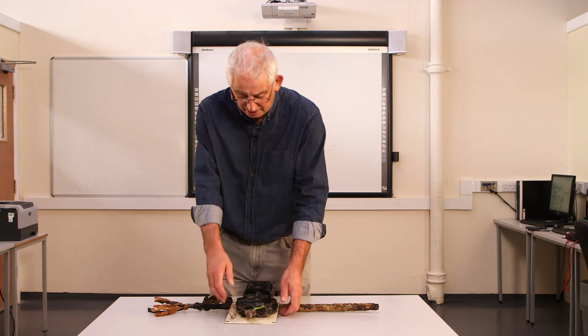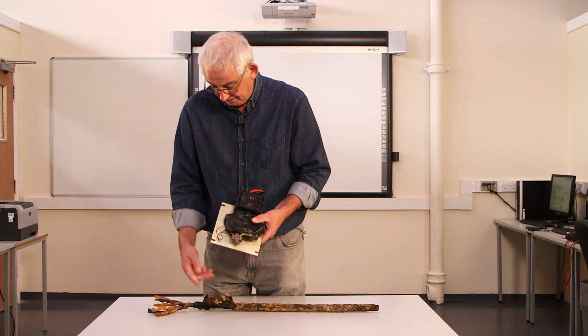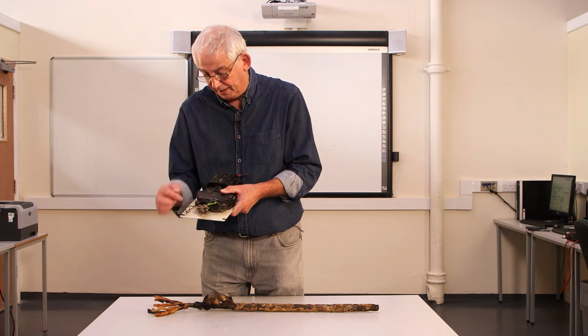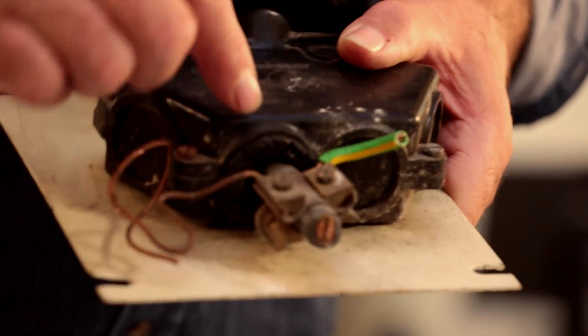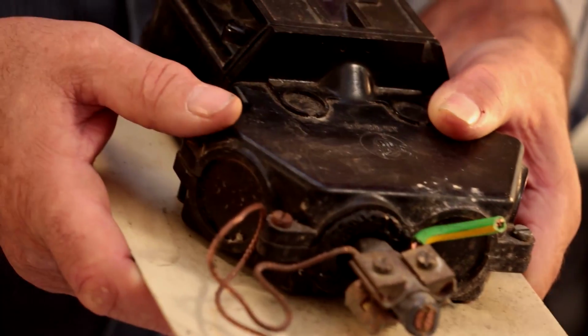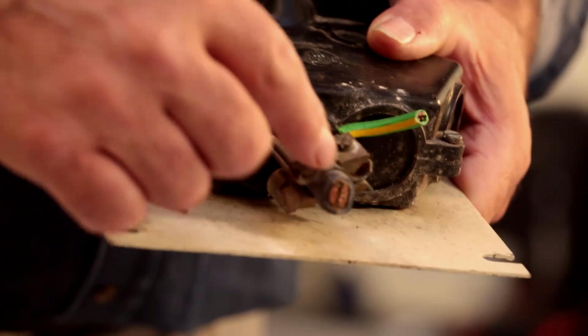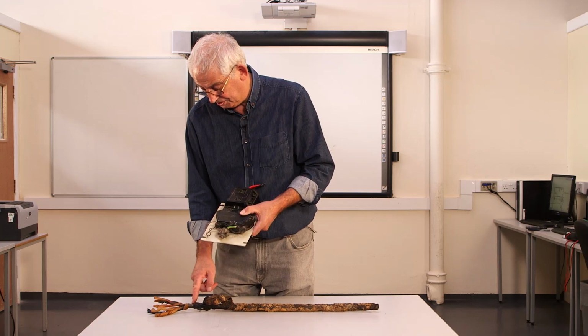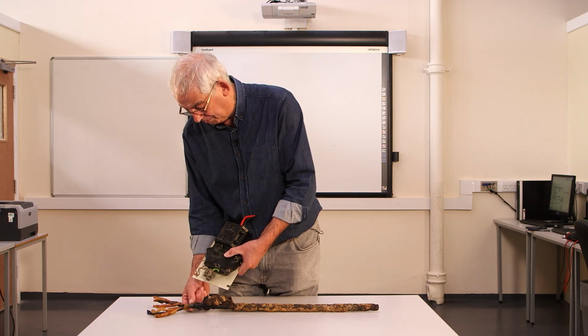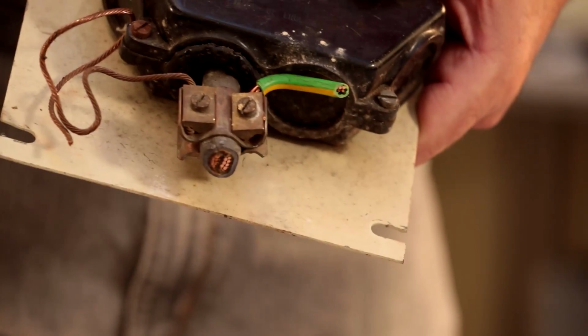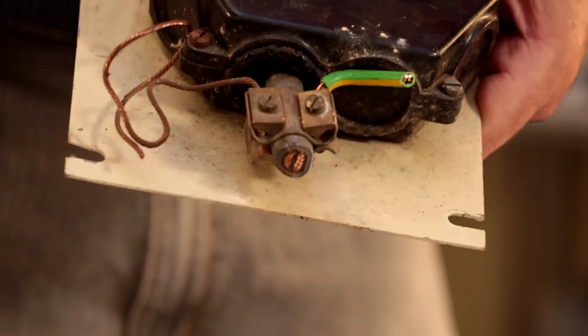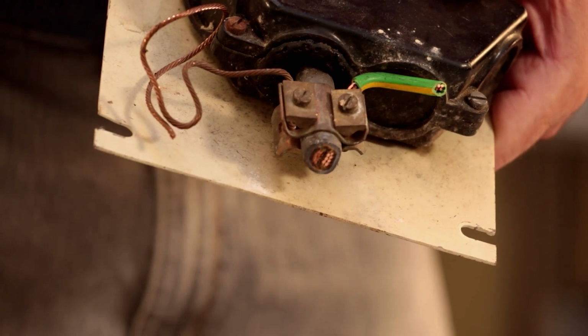When it comes into the house, you can see that the outer armour is stripped right back, so that what we're actually left with is the cores which are connected inside the service head, and our earth would be this sheath of the supply cable here, and we just connect an earth connection, not we, but the supply company would connect an earth connection to that.